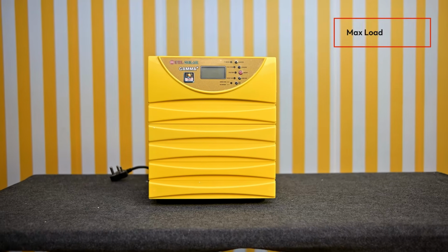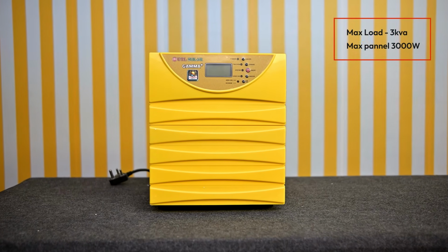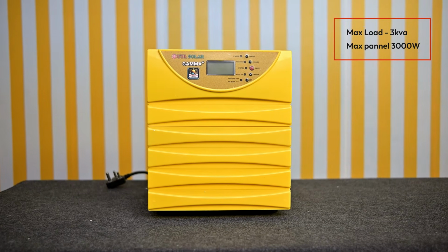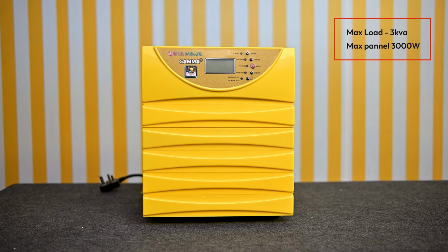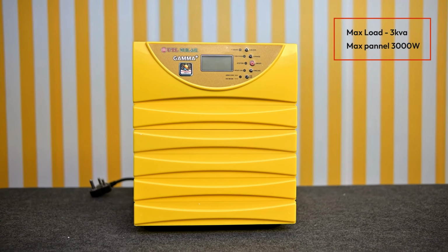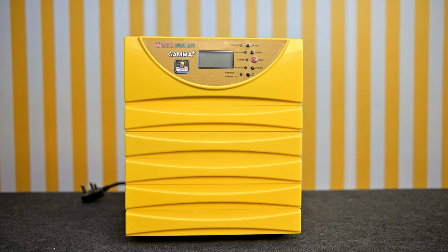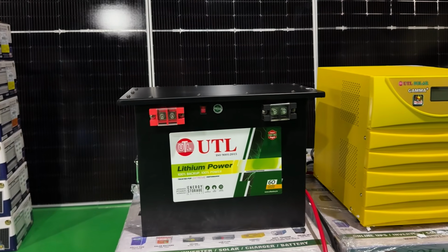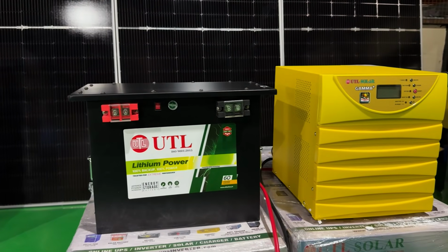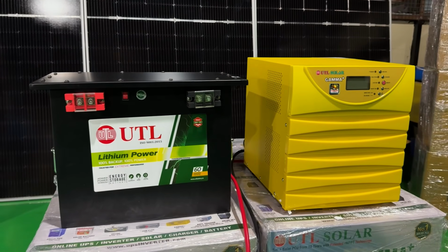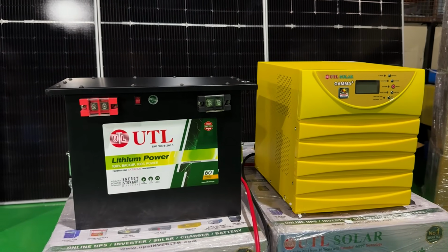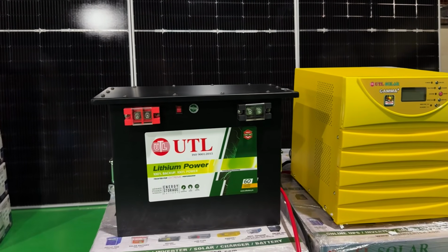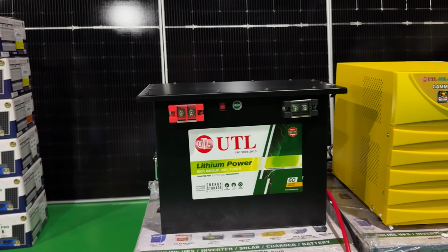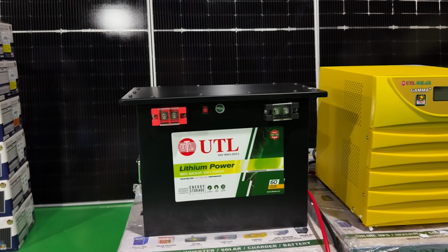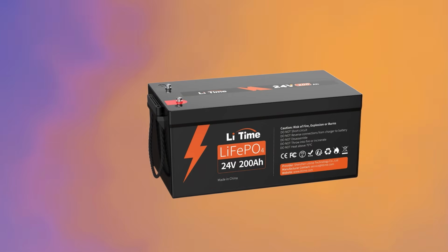Here I will give you an example again. UTL Gamma Plus has a 3400 model on which you can run a 3 kVA load around 2 kilowatts, and you can also connect 3 kilowatts of solar panels. Now UTL company also has its own 24 volt lithium battery. When you connect a 24 volt and 100 ampere hour battery and run a 2 kilowatt load, you get about 1 hour of backup. Now if someone wants to run a 2 kilowatt load for 2 hours, then they will need a 24 volt and 200 ampere hour battery.